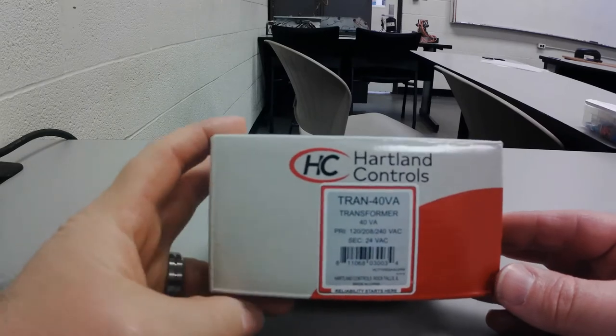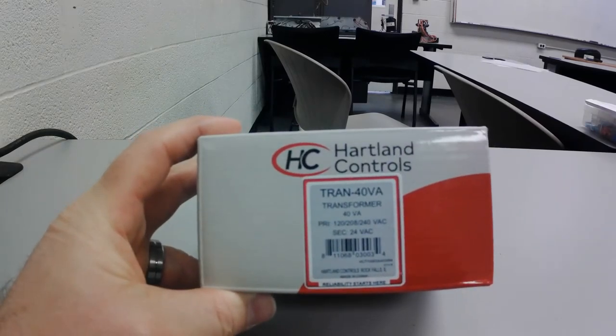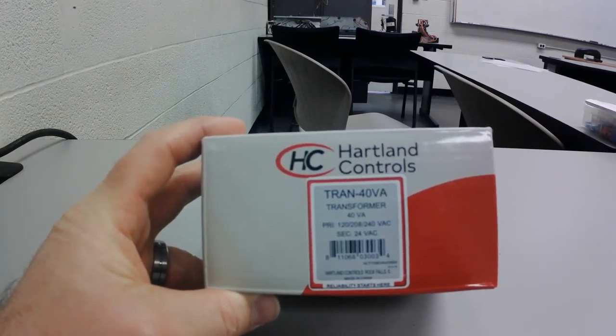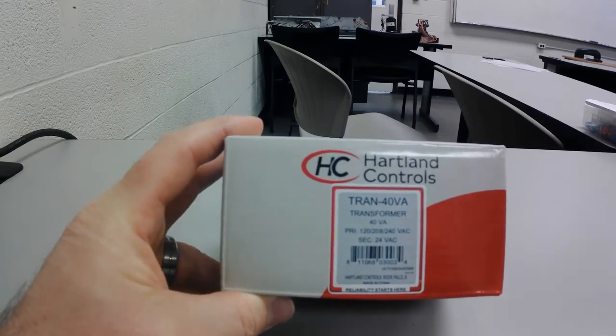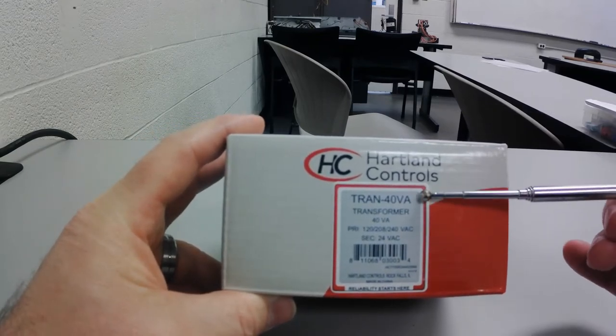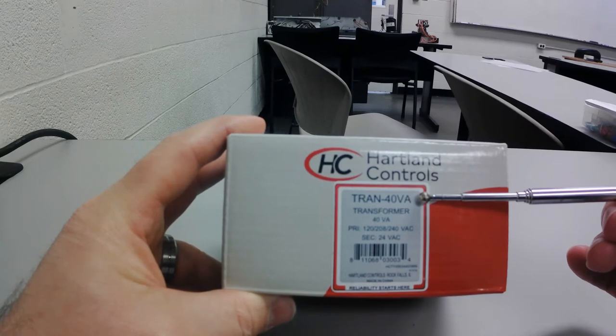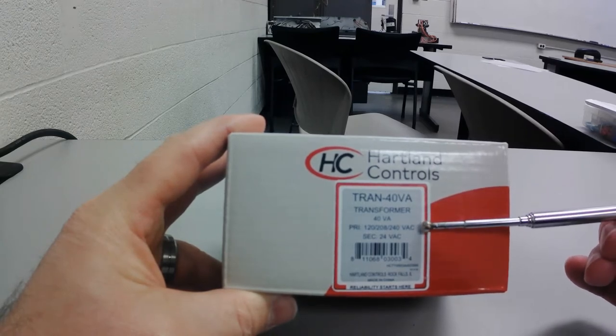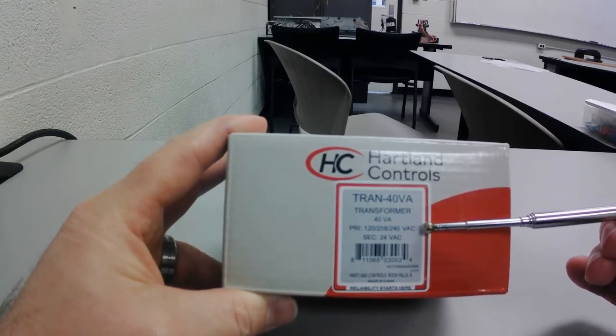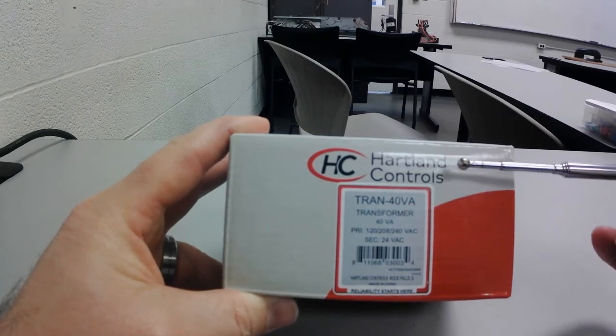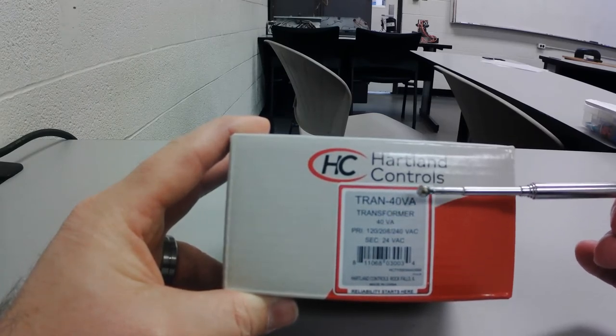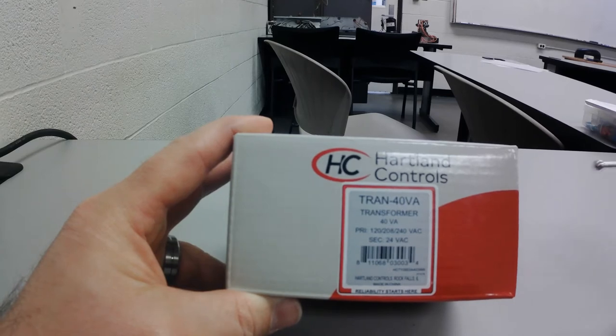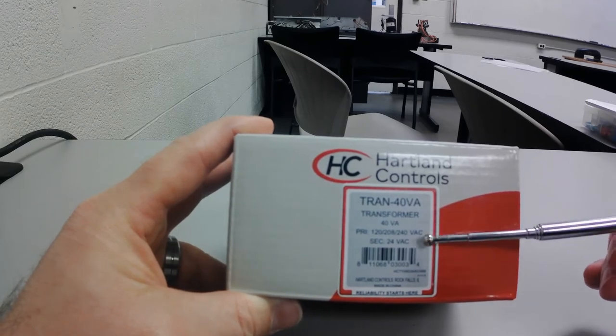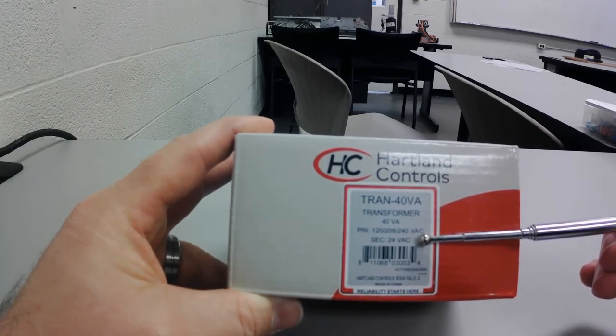So you can see here on this transformer, I've just got a box for a new one that I've pulled out. And if you can read the data plate or the sticker on here, this is a 40 volt amp transformer. You can see that the primary side has multiple high voltage inputs. We've got a 120 volt capability, 208 volt, and also a 240 volt. And no matter which one I use, I always get a 24 volt output.